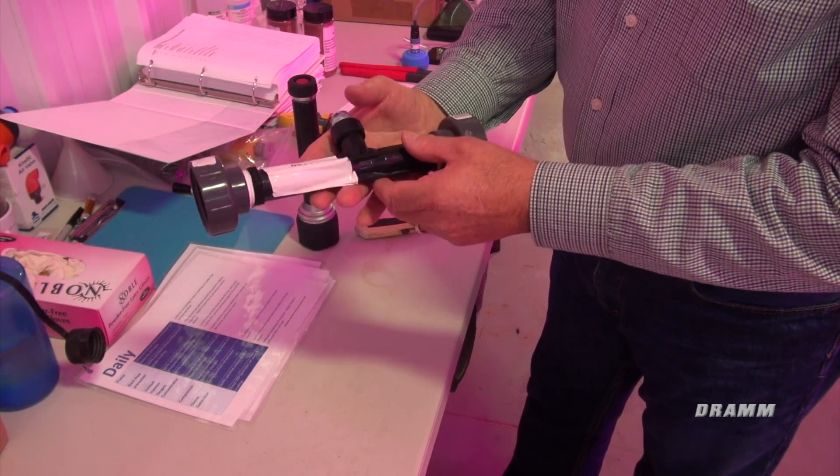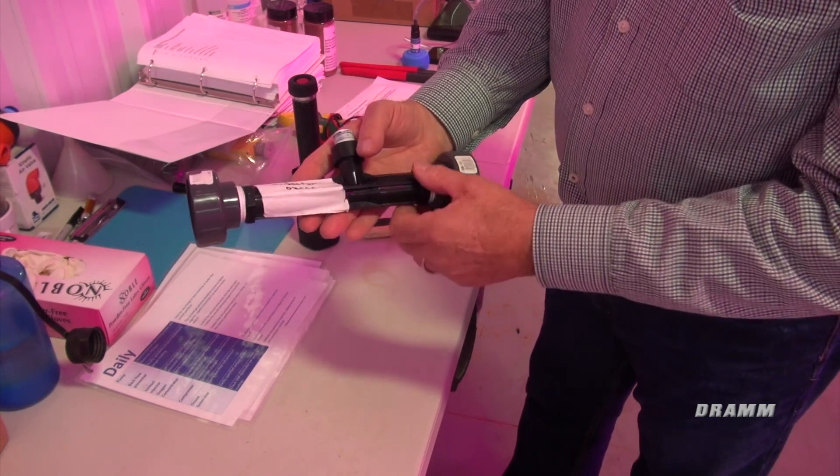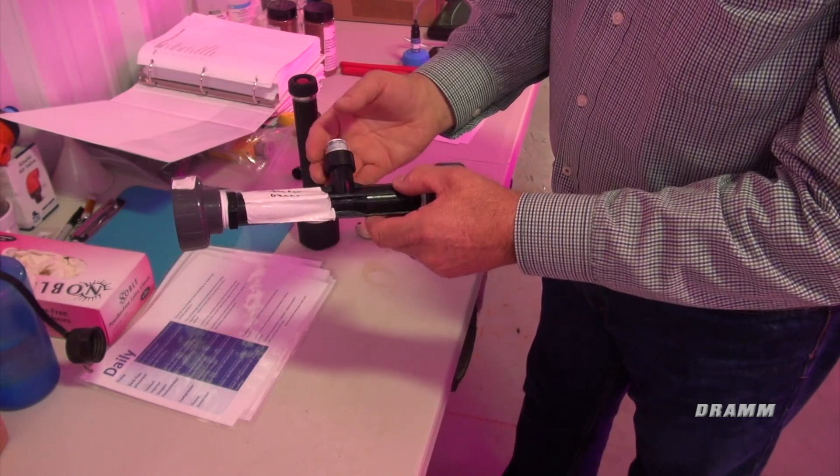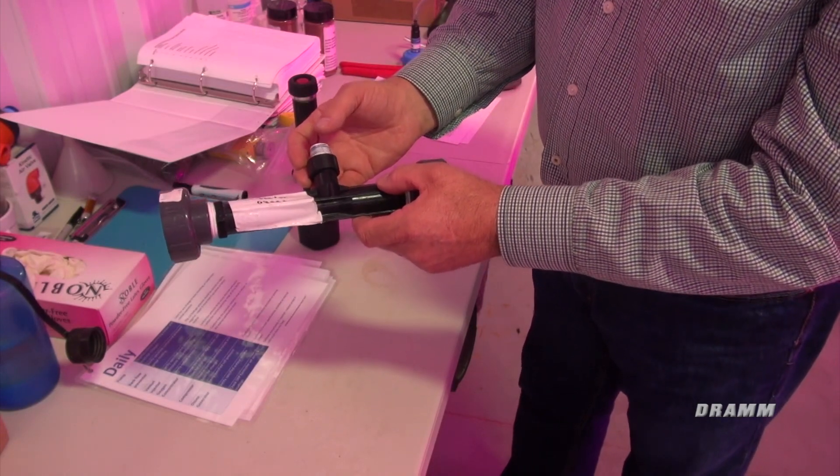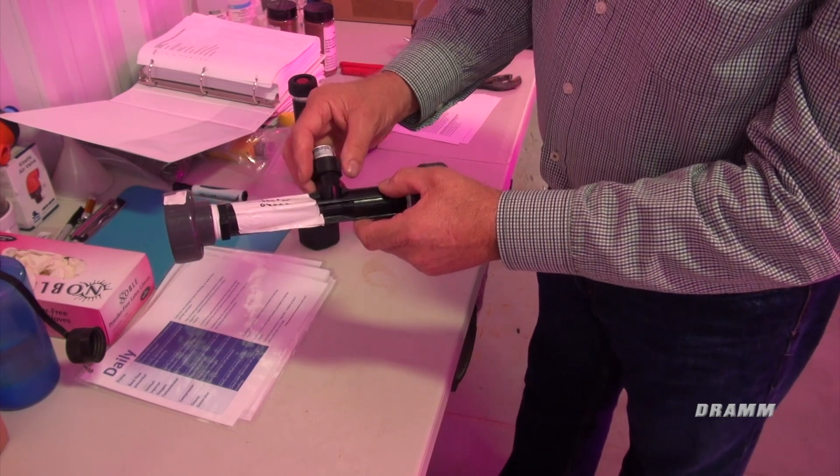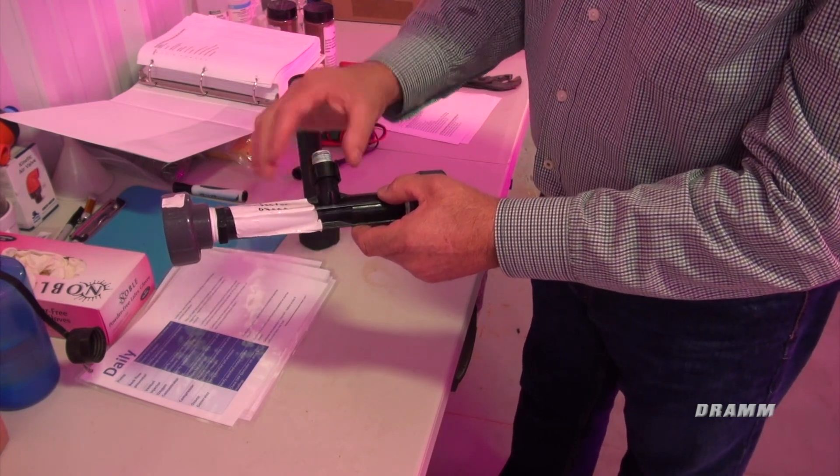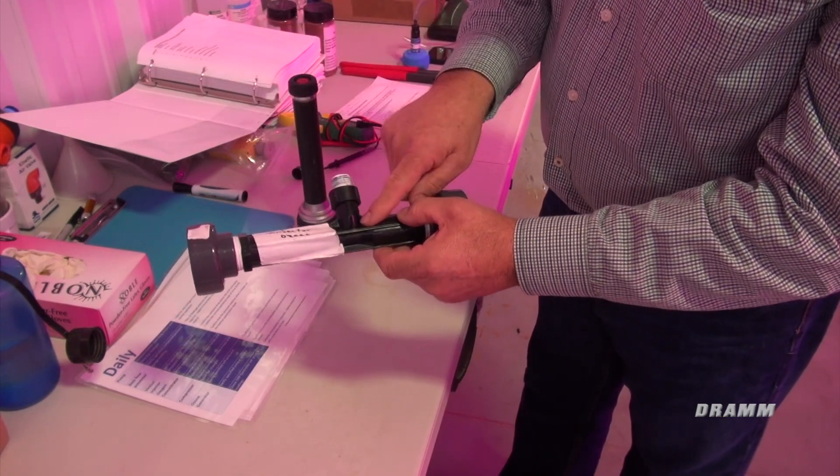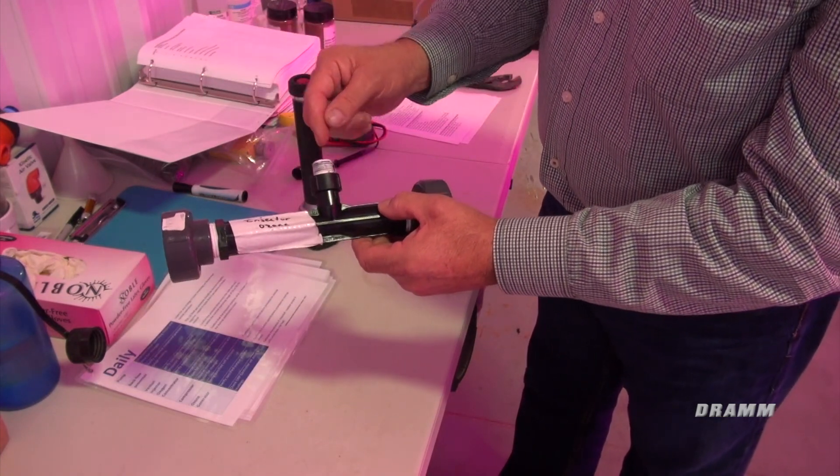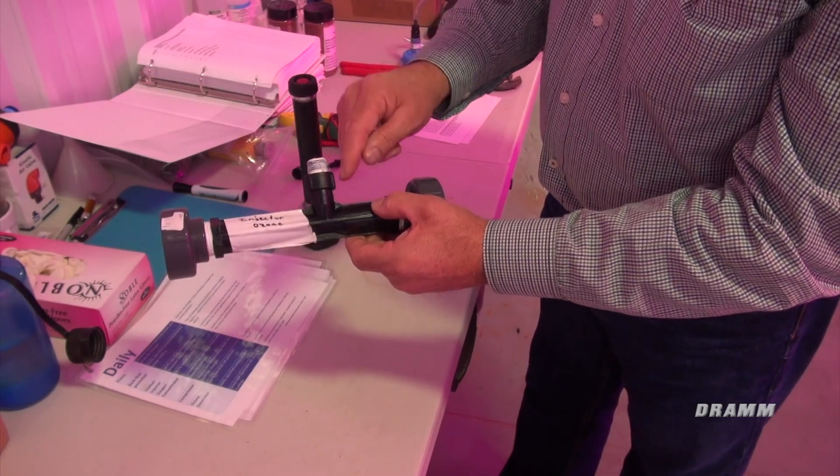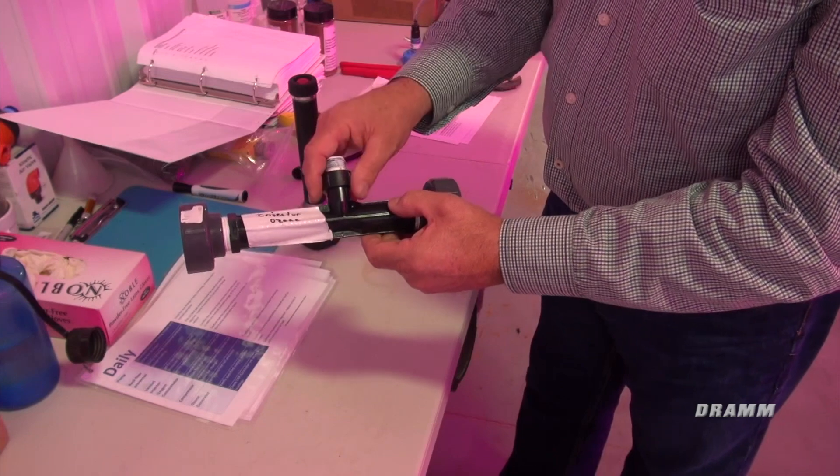This is the ozone injector. It's a venturi injector, and this is how we get the ozone into suspension, the ozone gas in suspension in the water. About 95% of getting the ozone into suspension occurs at this point right here. Water is flowing through here, creates a vacuum, and we draw the ozone gas through this tube, through a channel, and into the water.